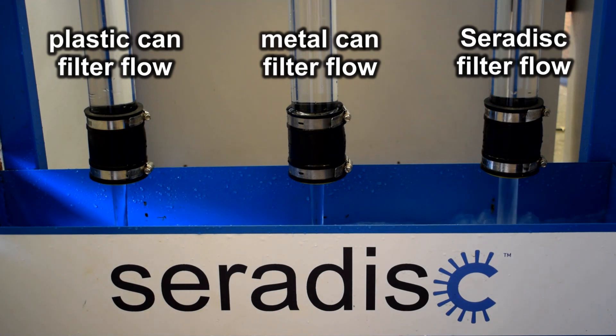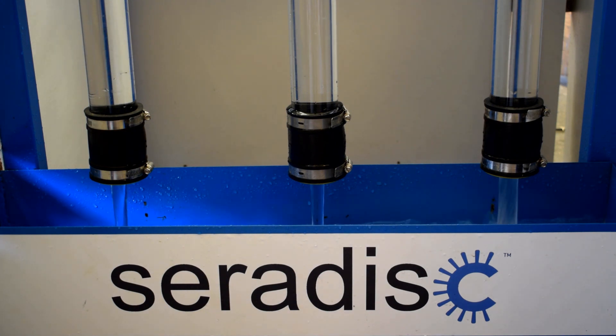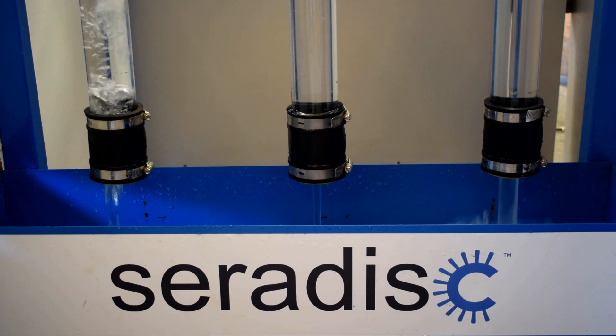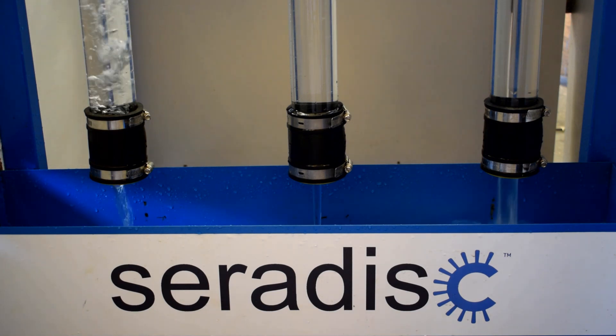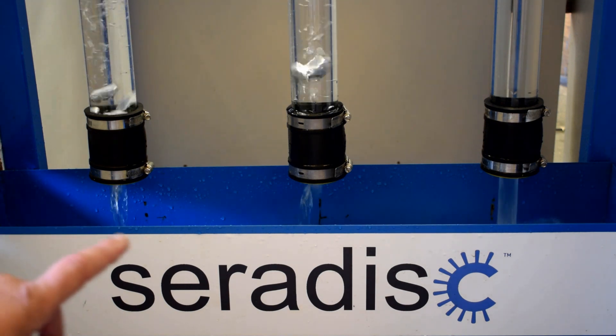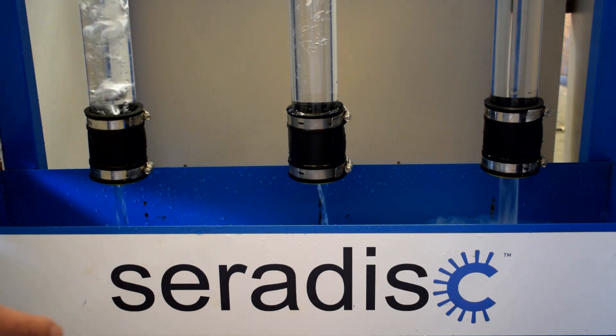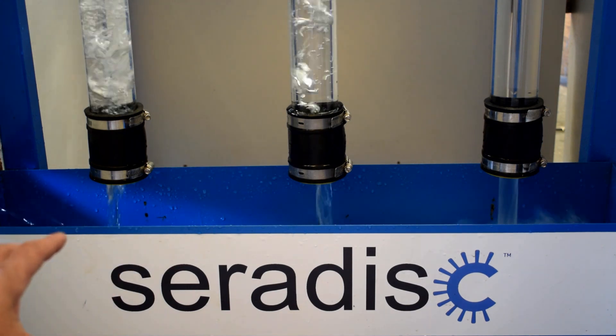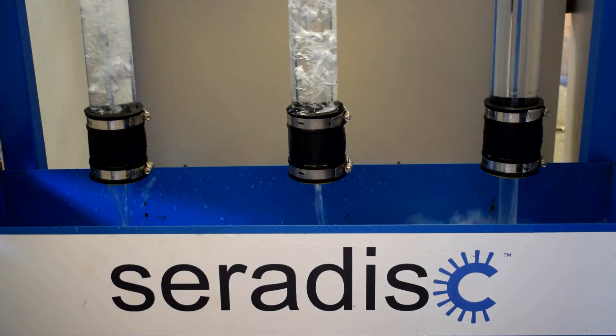You can definitely see the streams on the middle and the left hand side are getting much less, while the Seradisc ones are doing great guns. The plastic one has now stopped — it's blocked — and you can see the air bubbles coming up, which basically means it's so restricted it's hit vacuum. The middle one has started as well — those two have almost blocked at the same time.